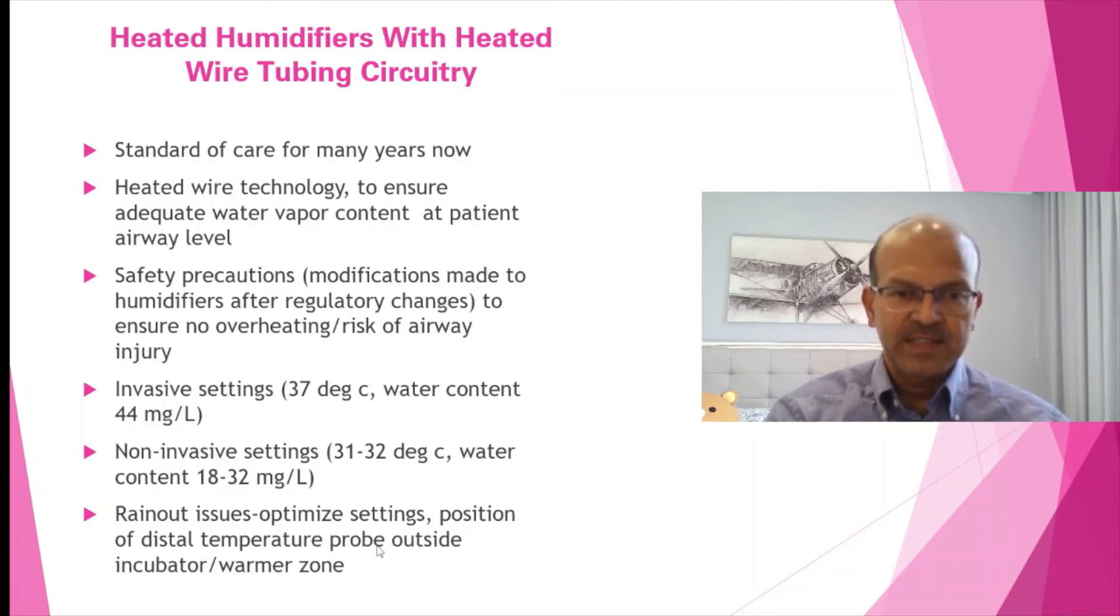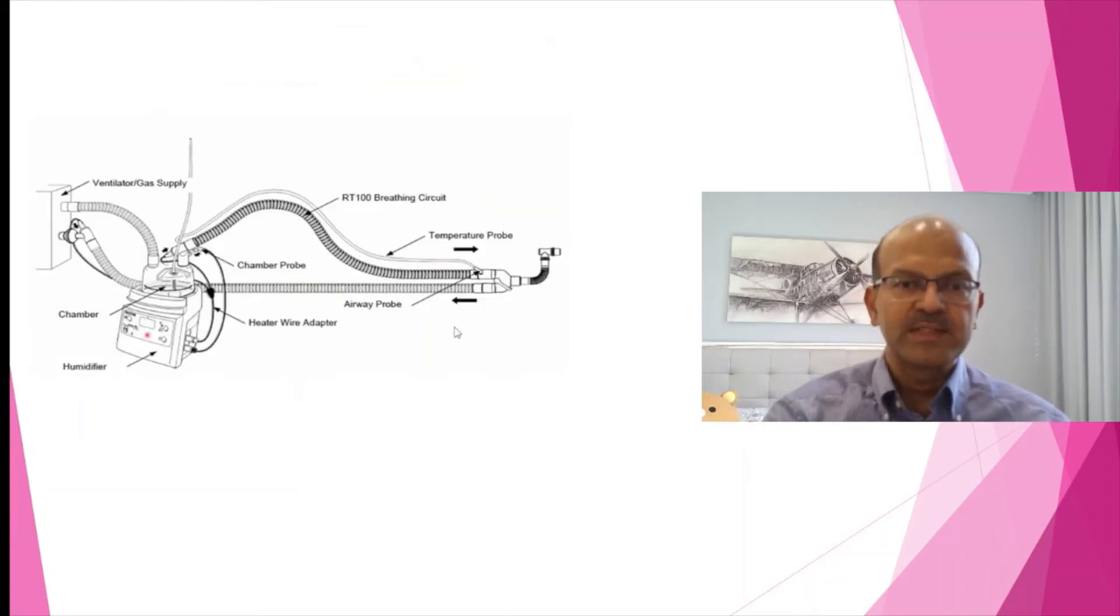The very important consideration here is that the distal temperature probe should be outside the incubator or warmer. Suppose this is the distal temperature probe, and you need a long enough extension beyond that so that the patient can be connected and this can stay outside the incubator or warmer. If it is inside, then you have a higher chance of rainout.